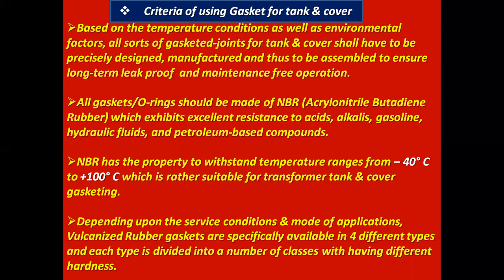All gaskets or O-rings should be made of NBR, that is acrylonitrile butadiene rubber, which exhibits excellent resistance to acids, alkalis, gasoline, hydraulic fluids, and petroleum-based compounds.